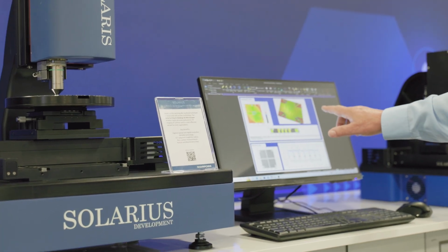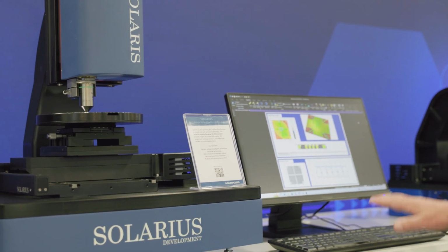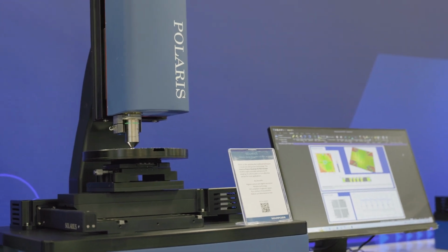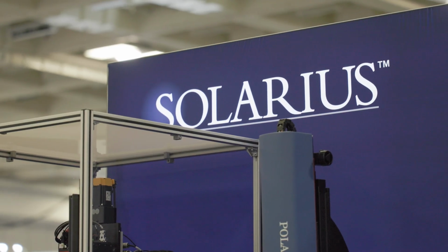So in the case of the Polaris, this is using chromatic confocal microscopy. So it's a much higher resolution system. In this case, we're measuring the integrity of the die that's on the circuit itself, or the wafer itself. So it's a very high resolution inspection, very detailed, of the wafers that's on there, higher than what you would have for something simple with a chromatic confocal system.